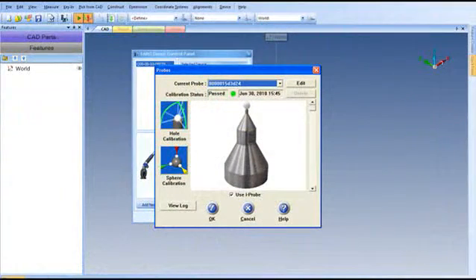From within that panel, navigate to the probe calibration, and we're going to begin with the hard probe calibration. Because it's necessary to take the hard probe off and then put the LLP on, you're reattaching the hard probe and you should recalibrate it. Select your hard probe from the drop-down and select hole calibration.